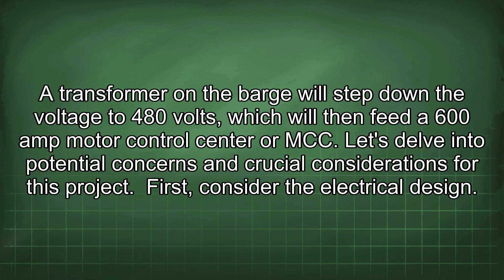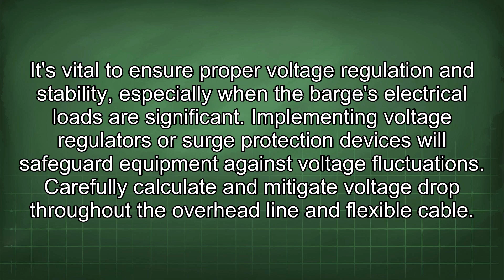Let's delve into potential concerns and crucial considerations for this project. First, consider the electrical design. It's vital to ensure proper voltage regulation and stability, especially when the barge's electrical loads are significant. Implementing voltage regulators or surge protection devices will safeguard equipment against voltage fluctuations. Carefully calculate and mitigate voltage drop throughout the overhead line and flexible cable. A well-designed grounding system is essential, providing robust protection against electrical faults and lightning strikes.